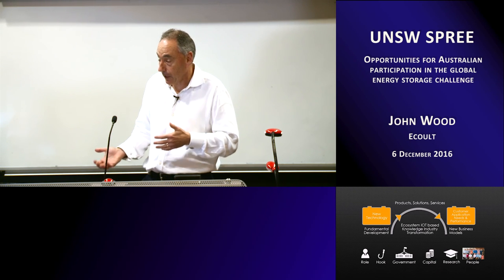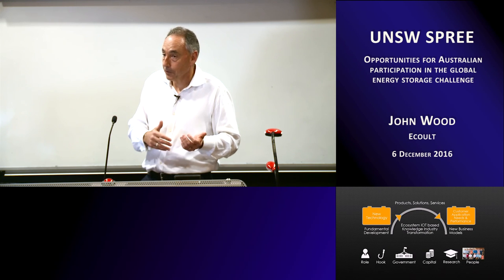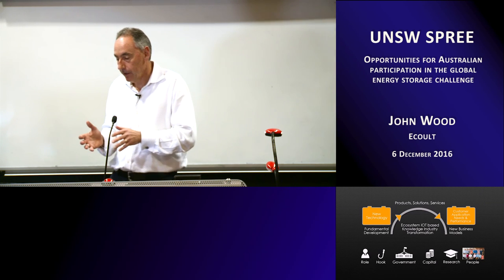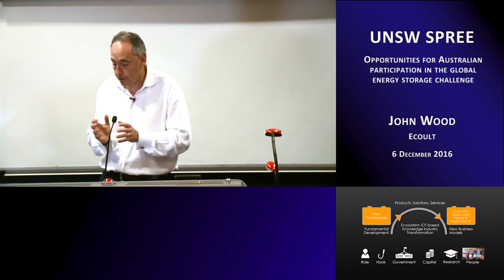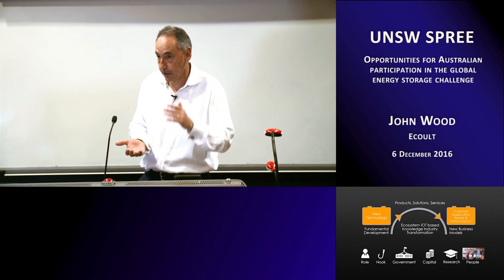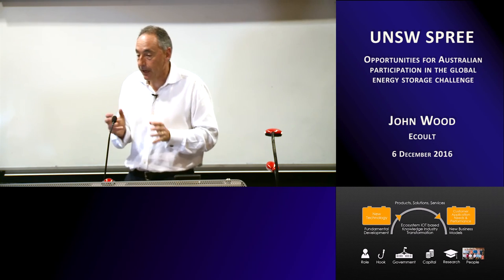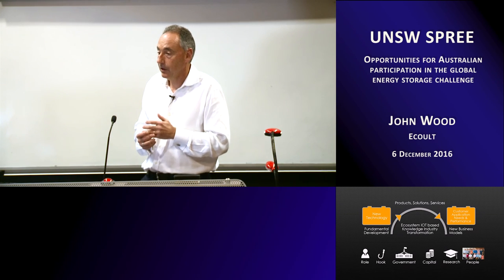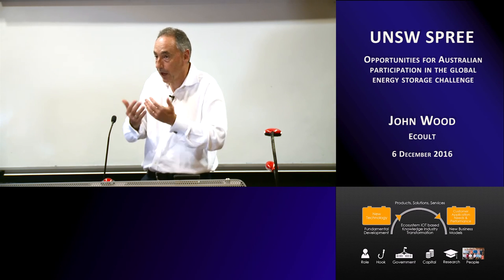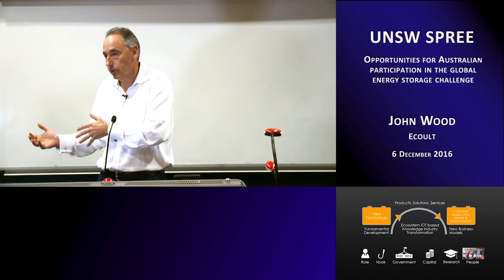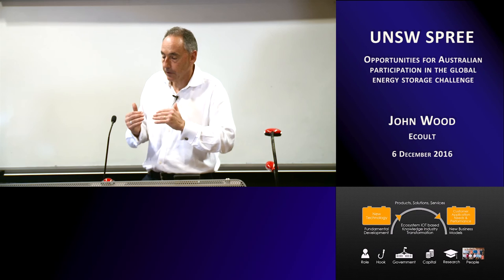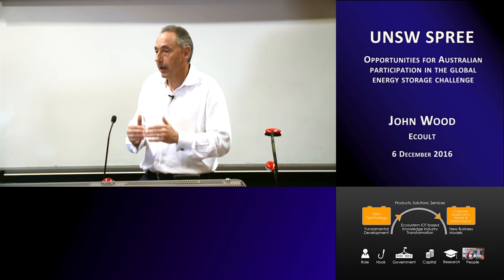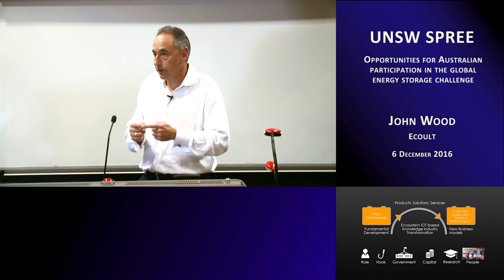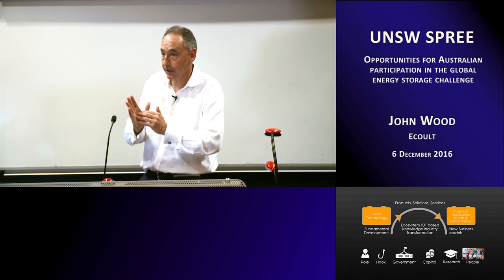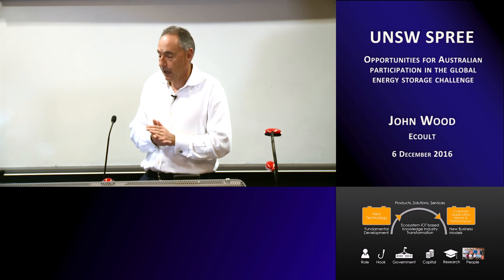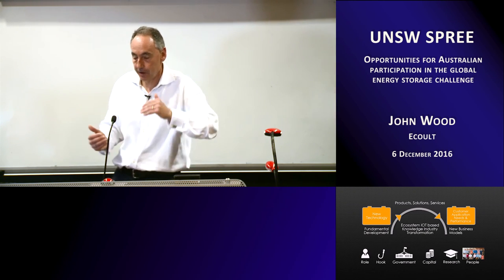When you take lead-acid technology and run it in a partial state of charge, you change all the rules in lead-acid chemistry. The primary method of degradation, if you're using the battery actively, is called sulfation, and that's the one that makes the capacity come down. The next two primary secondary degradations are just splitting of water — the rate of the oxygen reaction — and the rate of positive grid corrosion. Both of those secondary reactions depend on two things: the internal voltage of the battery, literally the potential between the plate and the electrolyte, which decides the rate of the oxygen reaction, and temperature.